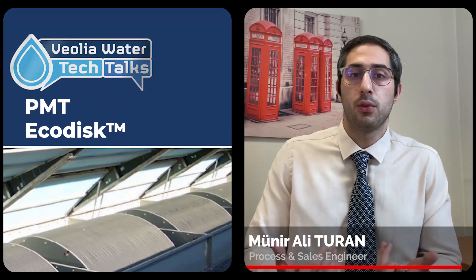The flexibility is definitely a key advantage of Ecodisk. Regarding low operation and maintenance, how would you describe the positioning of Ecodisk with focus on similar technologies in the market? Ecodisk has only a single gear motor which ensures the mechanical aeration of the biofilm. That is why it proposes 60-70% more optimized electrical consumption than conventional activated sludge, which generally uses blower systems to maintain aeration. This is also an important aspect for the electrical autonomy of the plant, because the minimal energy consumption will reduce the solar panel area required, optimizing the initial CAPEX for the end user. Ecodisk Solar proposes not only an electrically autonomous approach, but also an effective ROI for the future plant owner.